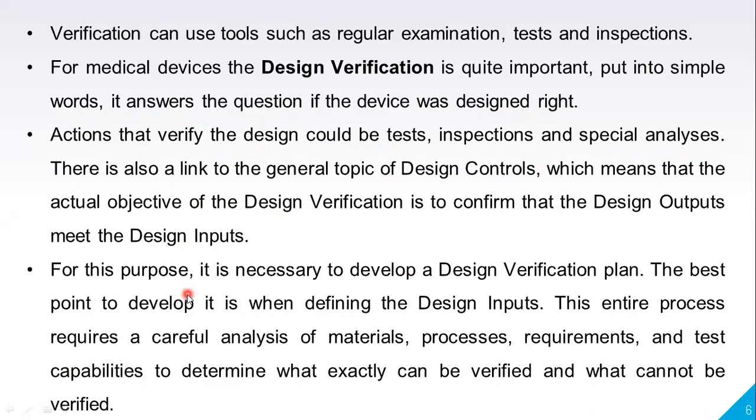For this purpose, it is necessary to develop a design verification plan. See, just as we develop a risk management plan first and finally go for the risk management report, similarly here also, first we develop a design verification plan. So in order to check each and every batch of a device, we have a proper plan. That plan is called a design verification plan. The best point to develop it is when defining the design inputs.